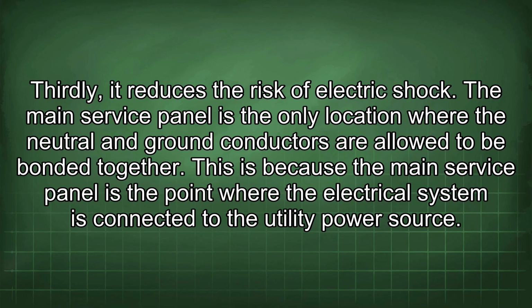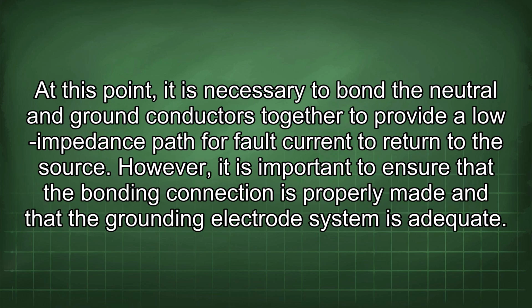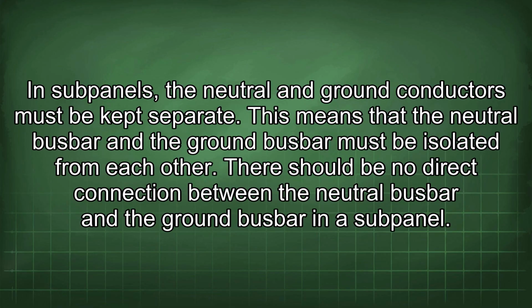The main service panel is the only location where the neutral and ground conductors are allowed to be bonded together. This is because the main service panel is the point where the electrical system is connected to the utility power source. At this point, it is necessary to bond the neutral and ground conductors together to provide a low impedance path for fault current to return to the source. However, it is important to ensure that the bonding connection is properly made and that the grounding electrode system is adequate.